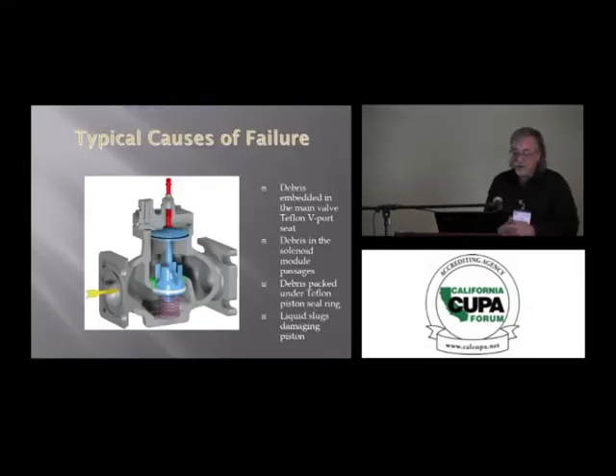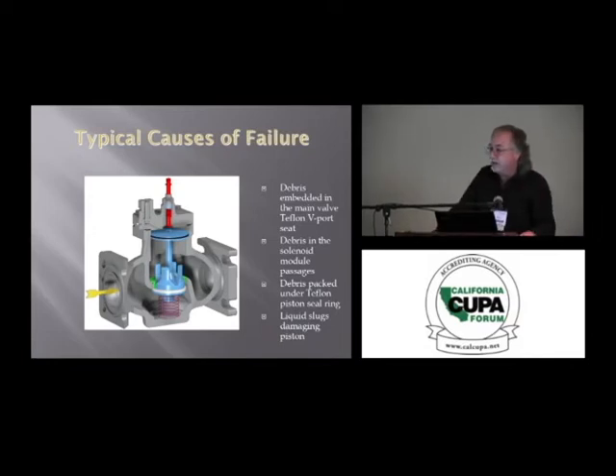Another thing when you're out there walking the systems is look at any point where there could be any gaskets or flanges bolted together. And like that solenoid I showed you up on the roof, look for oil. Look for white powder. That tells you that you've had a problem or you're going to have a problem. Now, it's not unusual for a system to have a little trace of oil here and there. Okay, but if you go in a system and you see oil all over the place, you can pretty much assume that they're not maintaining their system.